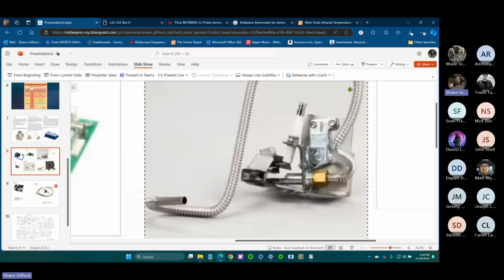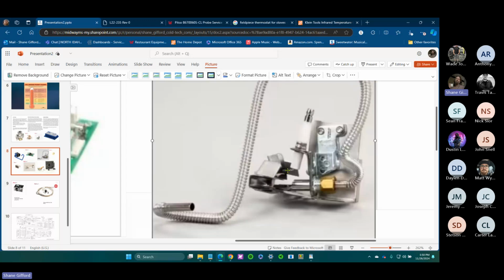this guy right here is hooked up to your pilot valve. That's what's going to be pushing out the pilot flame, and it's going to keep the flame steady in this area, or rather the gas. Right here is your electrode. It's got a little teeny tiny thing right there that when it gets voltage, 120 volts, it's going to directly arc to the little hood and create a spark. And when you've got this guy open and it's pumping gas inside here, and then you've got this guy right here creating a spark, well, now you've got fuel and you've got your ignition source. We should ignite and you'll have pilot flame.